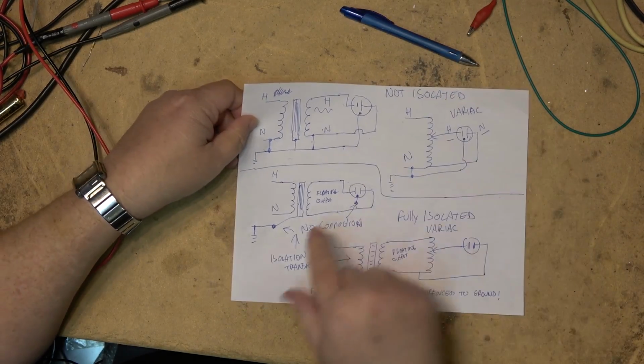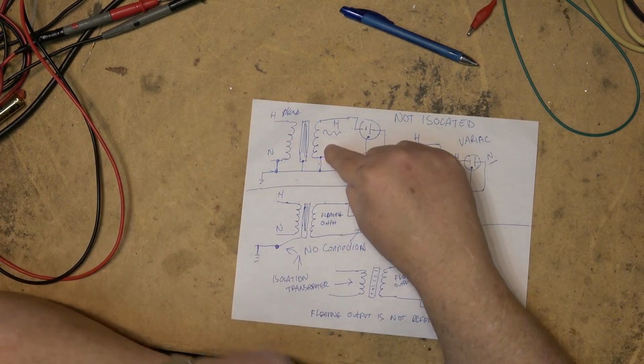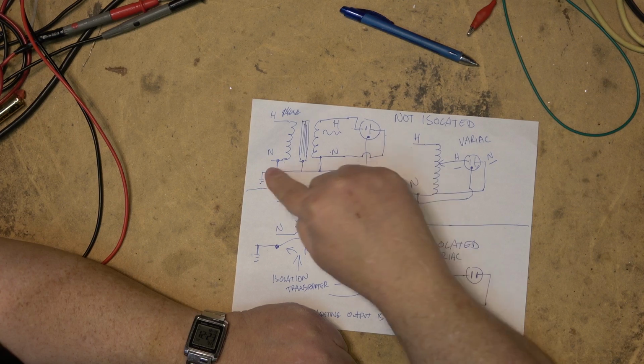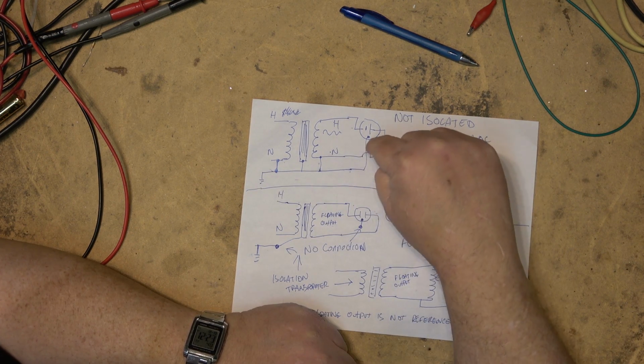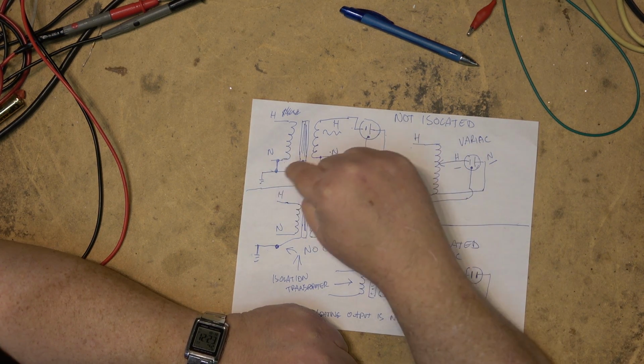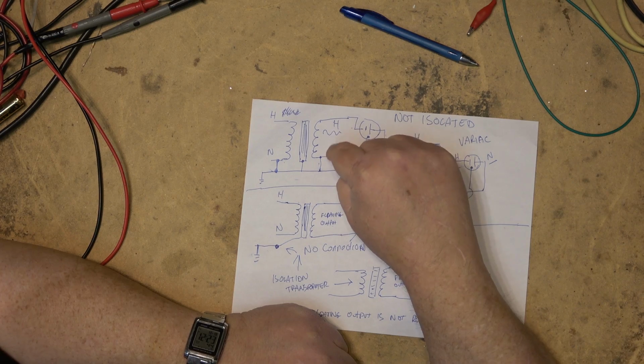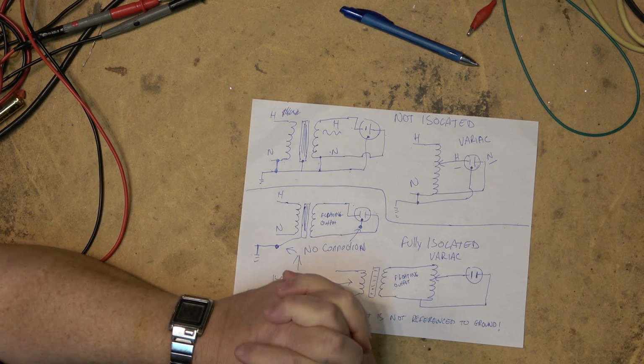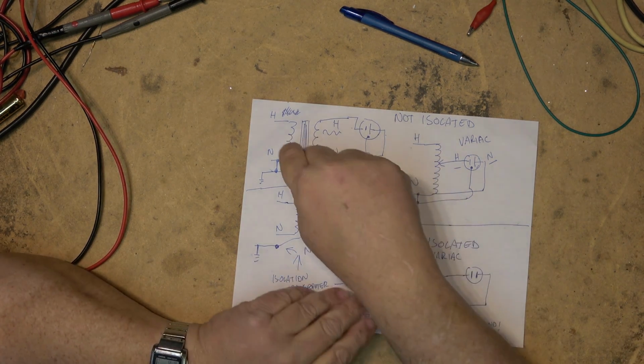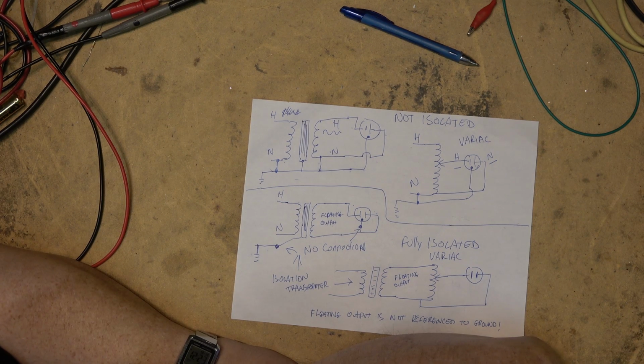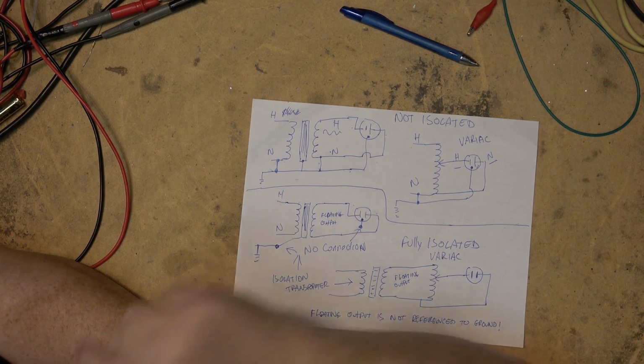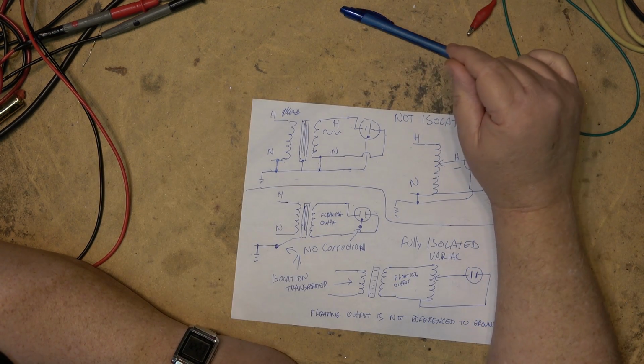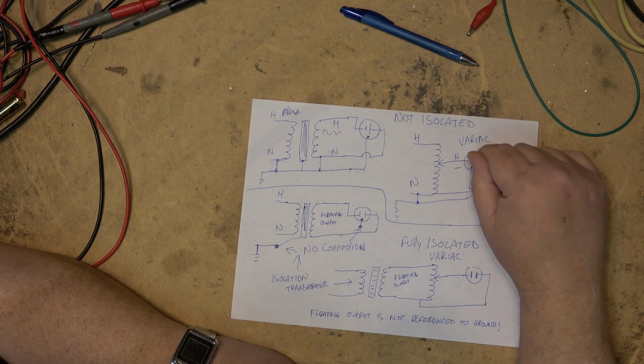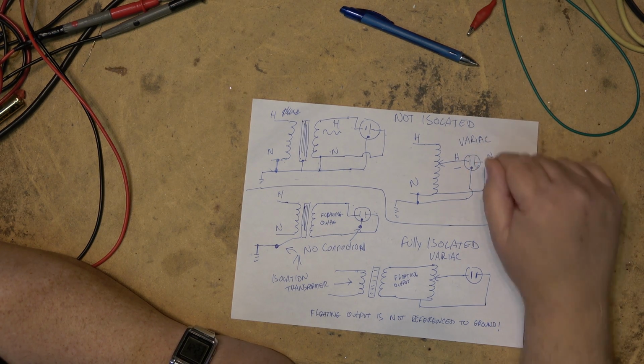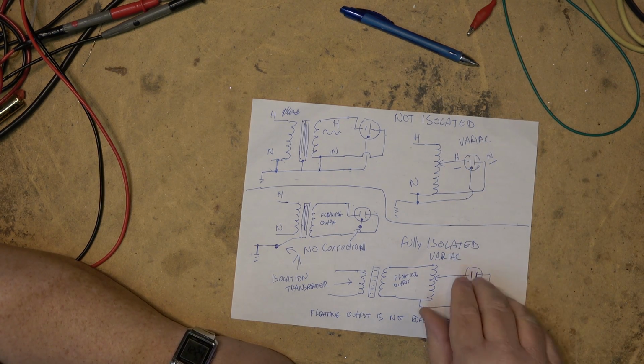That's an isolation transformer. If you're getting one, you've got to look for one like this. If you get one like this, open it up and cut any reference to ground. Cut the ground prong off here, cut the ground off on here, and cut the ground between the neutral and the secondary. And I've done one. I did a mod for a guy who bought one in this configuration, and he shipped it to me to have the grounding removed. Another thing to point out: when you're plugging in test equipment, you can plug your test equipment into this output as well, or not this one, but this output here, with no ground.